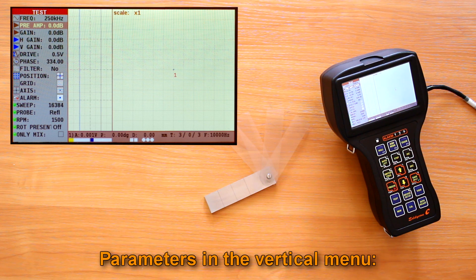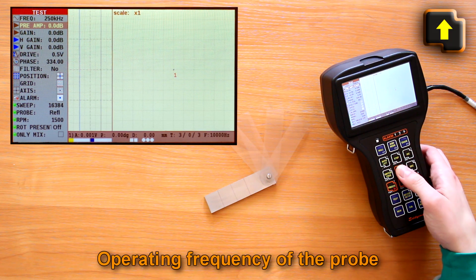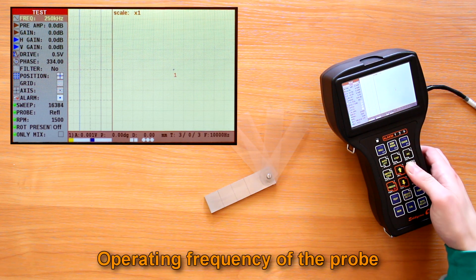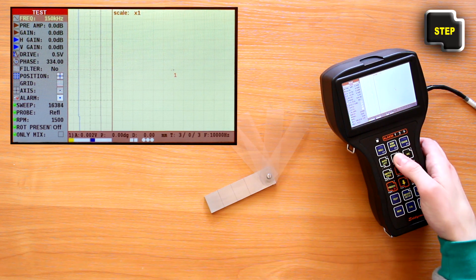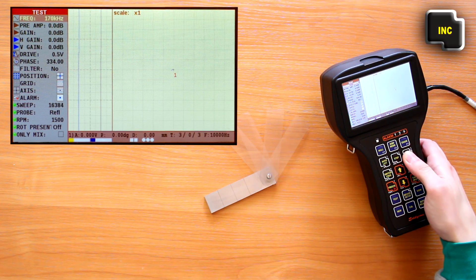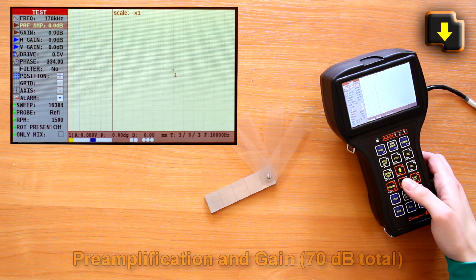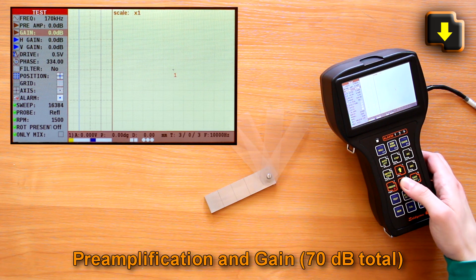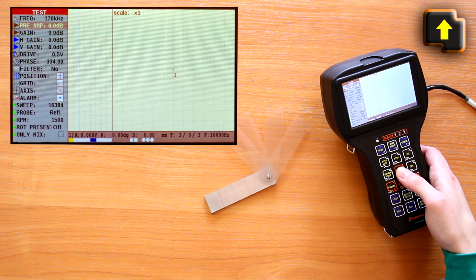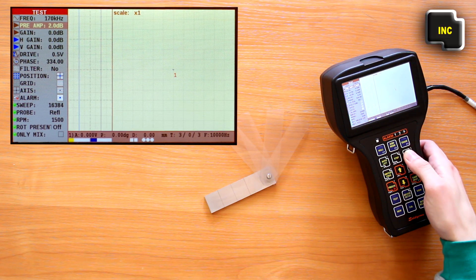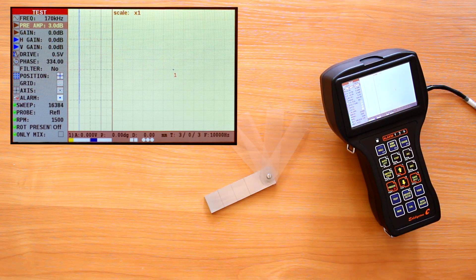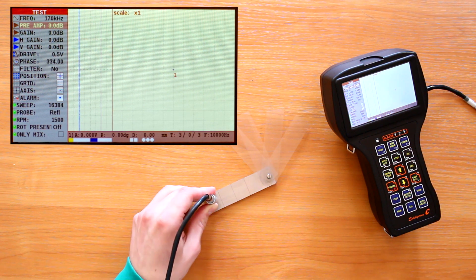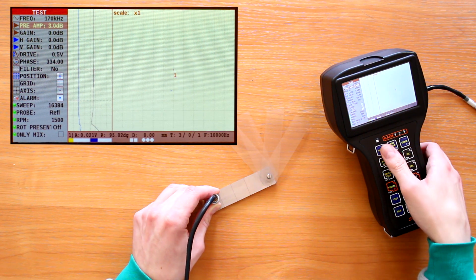Let's review the parameters in the vertical menu. Operating frequency of the probe. The range of frequencies is indicated in the registration certificate for the given ECP. Preamplification and gain. In order for the change preamp value to take effect we need to perform balancing pressing F1.